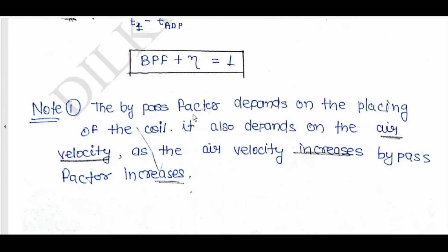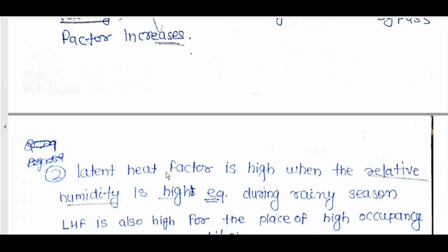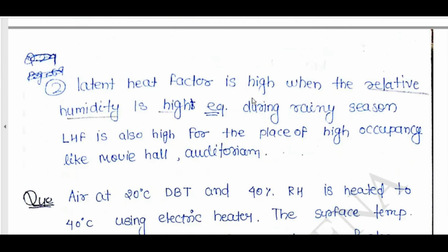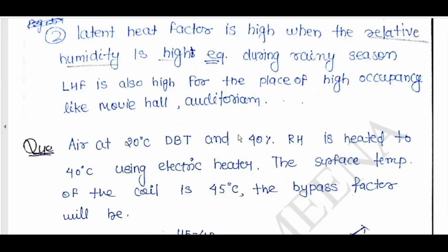The bypass factor depends on the placing of the coil. It also depends on air velocity. As air velocity increases, bypass factor increases. Latent heat factor is high when relative humidity is high. For example, during the rainy season, LHF is high. It is also high for places of high occupancy like a movie hall or auditorium.